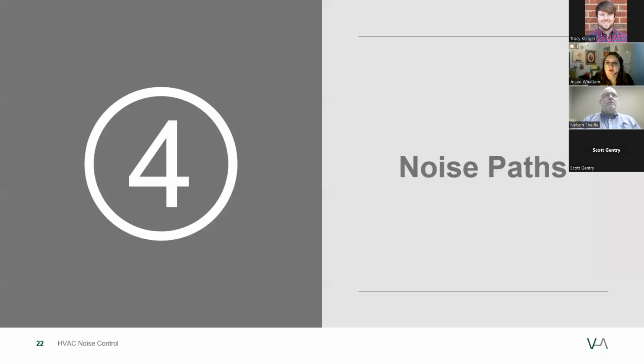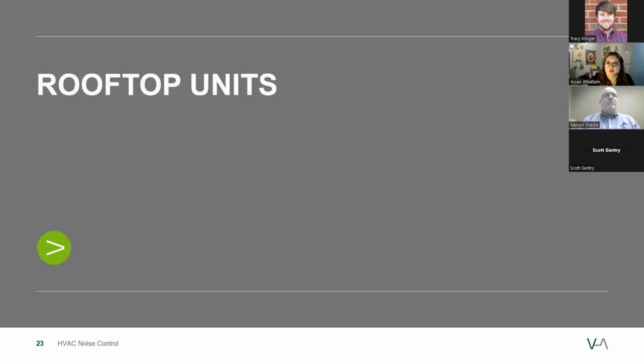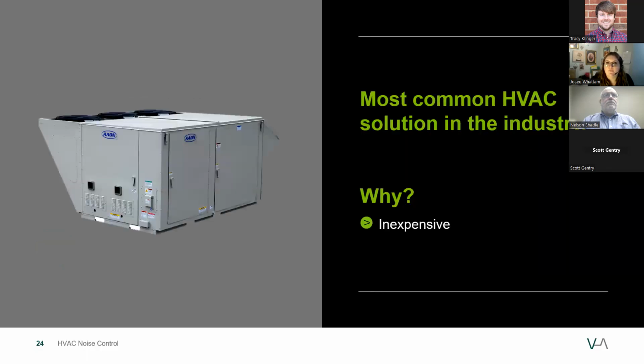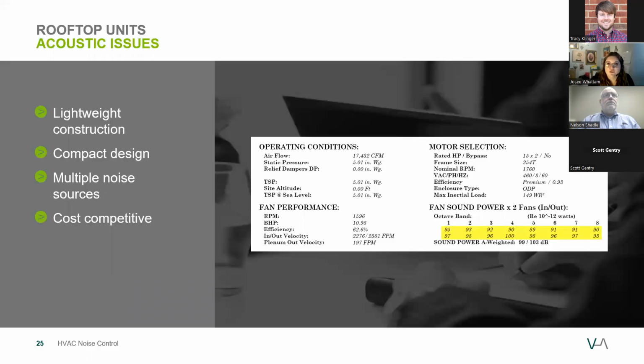So let's talk about the noise paths, which, if you recall, was one of the steps in effective noise control design I mentioned earlier. I'm going to use an RTU example to explain this. So RTUs are the most common HVAC solution for one major reason, because they're inexpensive. Unfortunately, for this reason, though, the typical RTU has high sound power levels. If we break this down, we can see why.